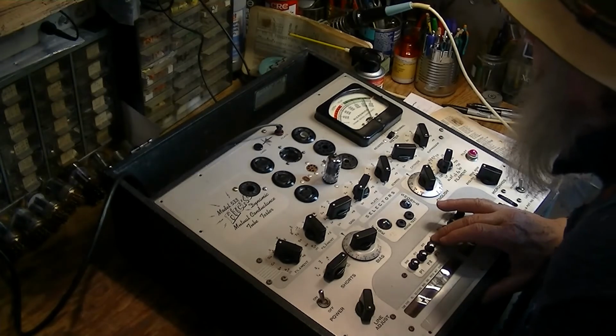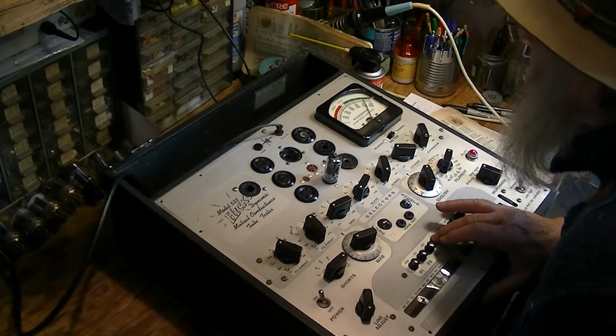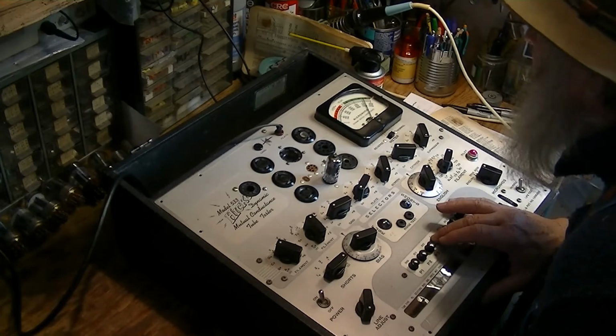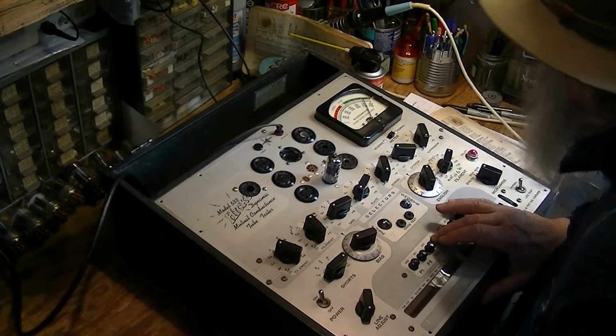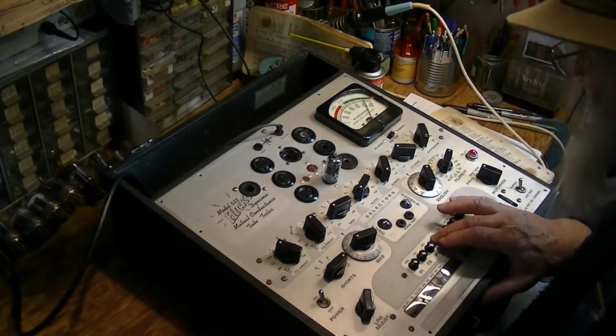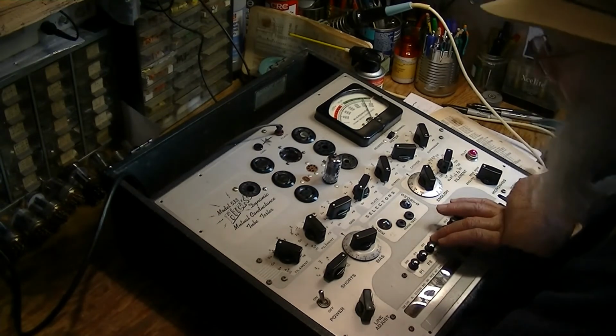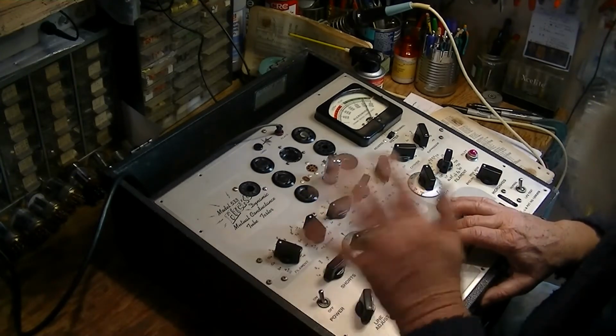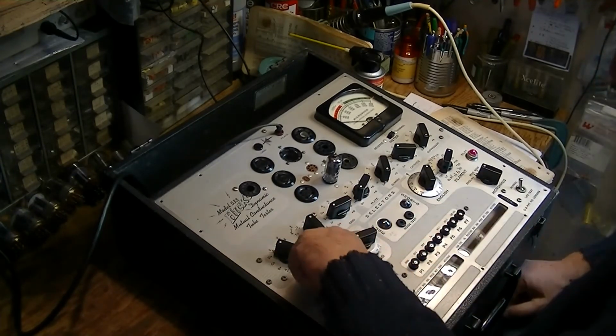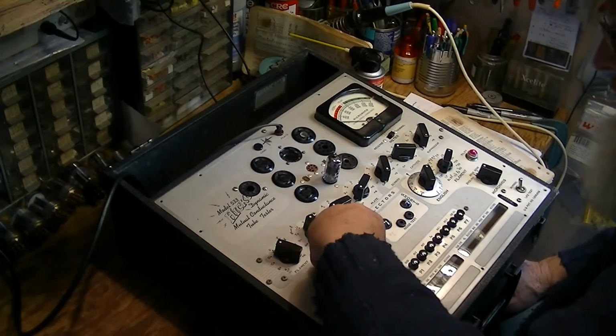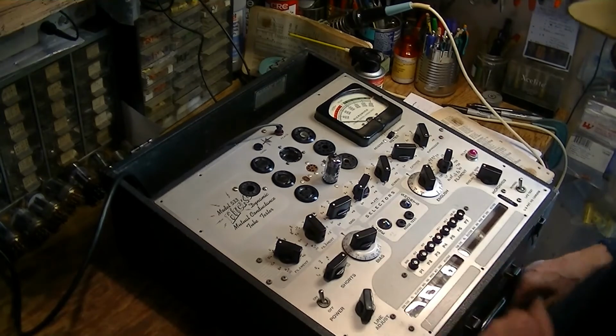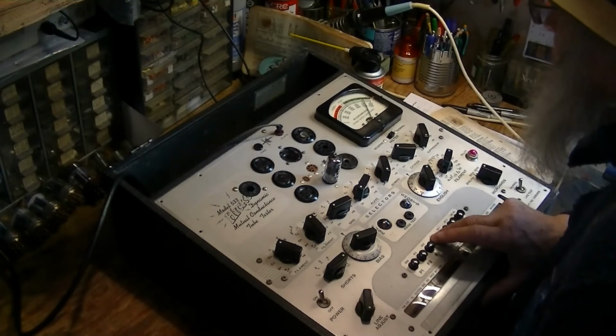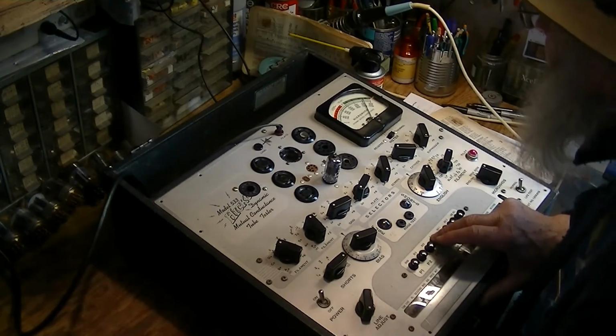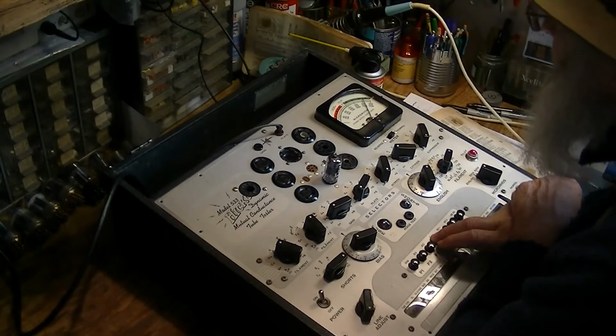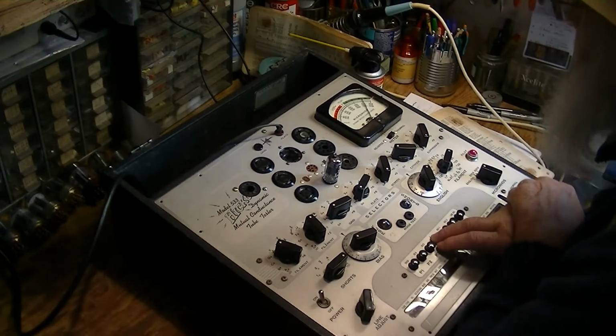Okay, this came up as 2575, not quite 26, but 2575. And that's good. If the tube's gassy, it's going to show up on both sides, so you don't have to worry about that. We can do the short test for this one as well, because it's a different section of the tube, and the short test is fine there. The filament life is not going to be any different because it's the same filaments for both sections. Doing the same thing, it's barely dropping 50.